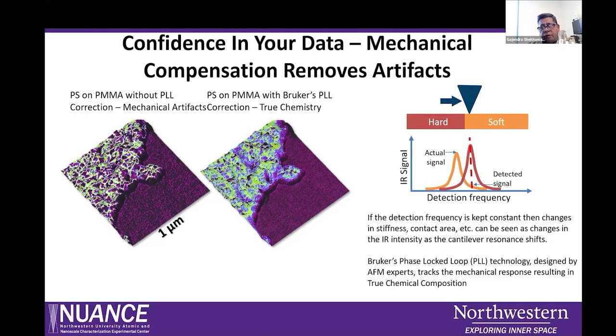So here the system uses the phase locked loop. What it means is that if the probe is interacting with different regions of the sample which have a different density variation, for example, there is a shift in resonance. The phase locked loop just gets activated and tries to maintain the cantilever resonance. So we make sure that we are getting the true chemical information just at the tip-sample interaction interface, not the variation because of thermal, mechanical, or contact area differences. On the left, you can see the image without the phase locked loop, and on the right, which is a much cleaner, nicer image, is with the phase locked loop, which represents the true chemistry of this imaging technique.